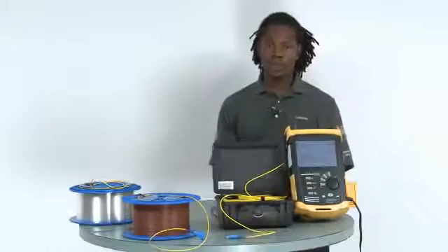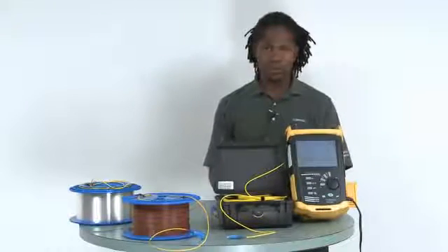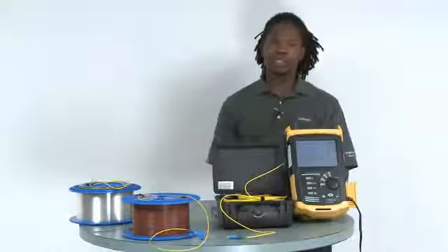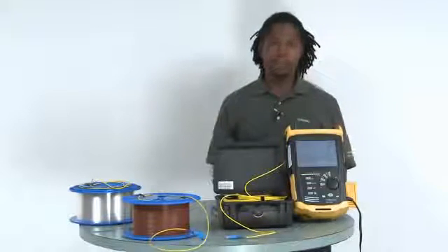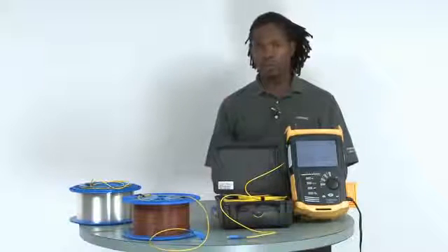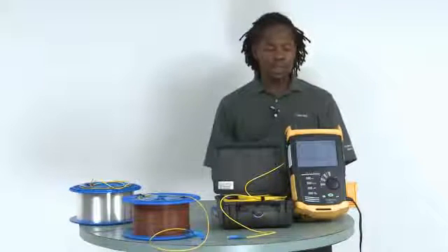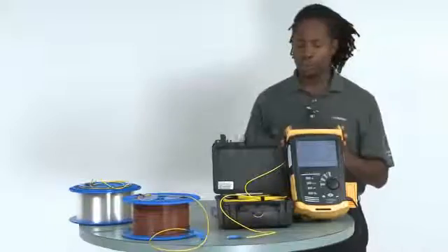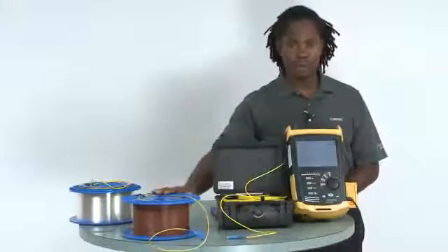There are two common methods of testing a fiber optic link. One involves pass-through testing, which gives you attenuation values for the whole link. The other method involves an OTDR, or optical time domain reflectometer if you prefer. The OTDR, when in use, is paired with a test fiber box, and of course the test fiber box has to be of the same fiber as your system you'll be testing.